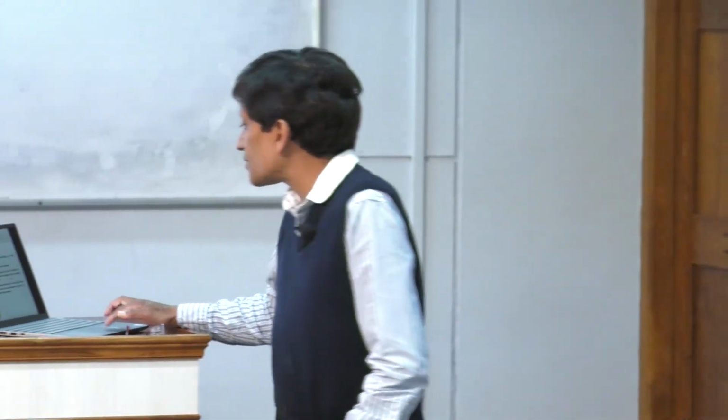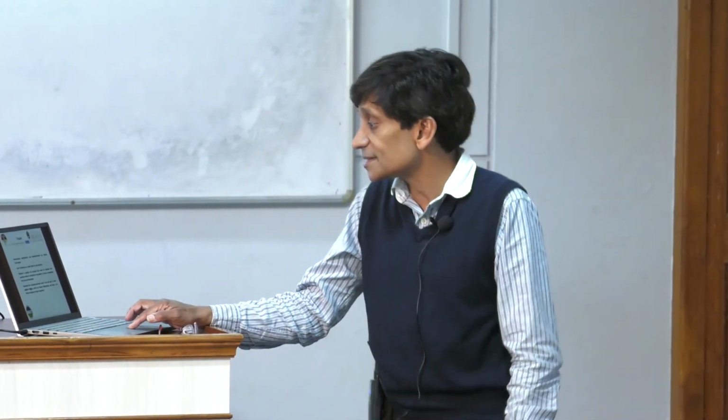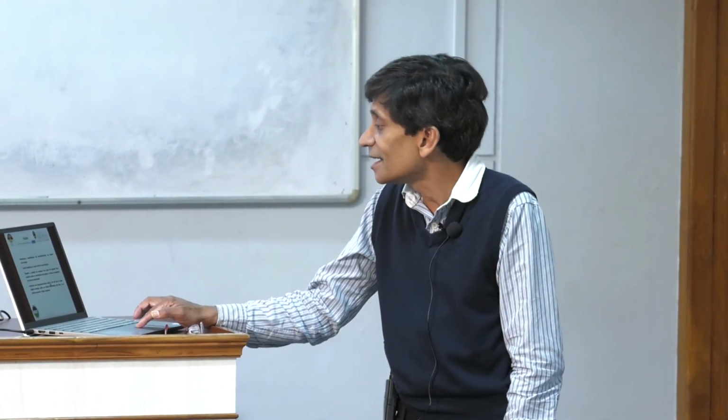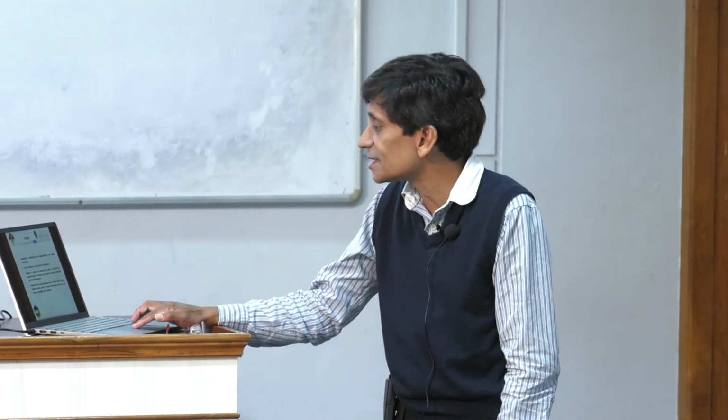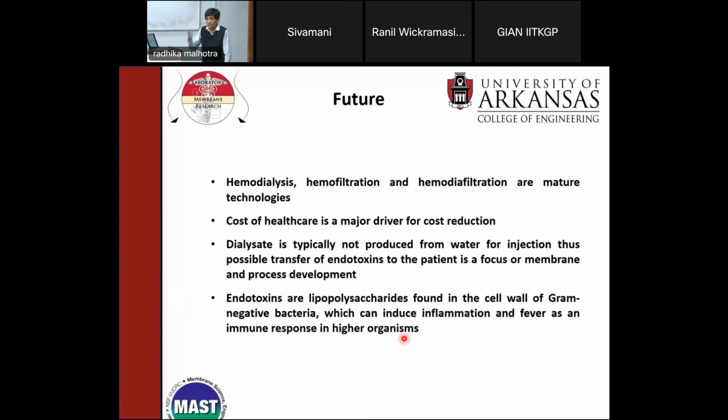So the problem is you can have endotoxins. I wasn't sure if you knew what endotoxins are. So endotoxins are lipopolysaccharides found in the cell walls of gram-negative bacteria, which can induce inflammation and fever as an immune response in humans and higher organisms. So there could be endotoxins in this water, okay? And they will not be removed because it's not water for injection.